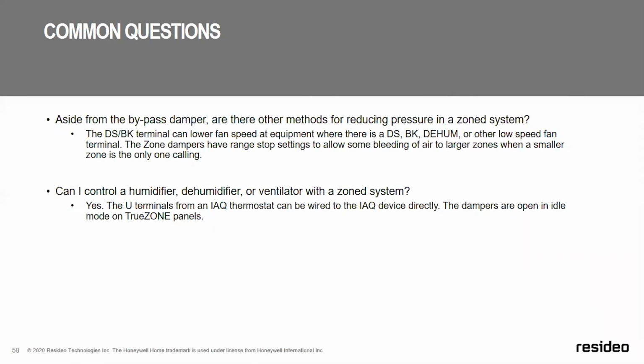We don't typically see a need to have separate points of control for a humidifier, dehumidifier, or even a fresh air damper throughout a home. It works a little differently than the temperature controls. So our recommended method, and what works fantastically in my market, is to use one of the thermostats in this system to control your IAQ equipment. There are several ways to do it. We have some RedLINK thermostats that can be operated with equipment interface modules if you don't have enough wires, or any wires, in the zone where you want to control it. And most or all of our IAQ thermostats have U terminals that can be used to control an IAQ piece of equipment.